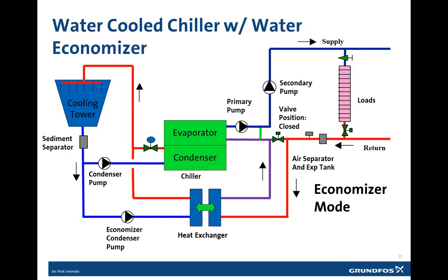Now, the addition of a secondary loop for a configuration of piping, as discussed earlier, means the addition of a pump to the loop that connects the heat exchanger to the chilled water return. So the addition of this pump allows the heat exchanger loop pressure drop to be disregarded in the calculation to size the chilled water pumps used in normal operation. So this is important to limit the potential energy losses of the system configuration while taking advantage of the energy savings of the economizer cycle.